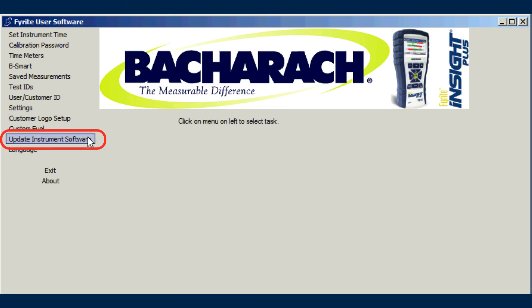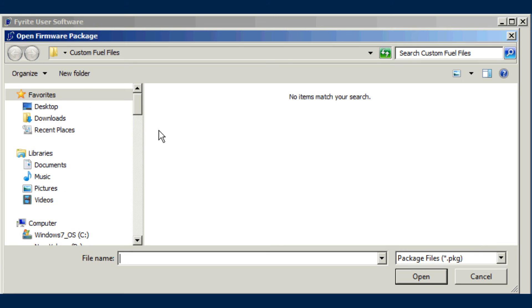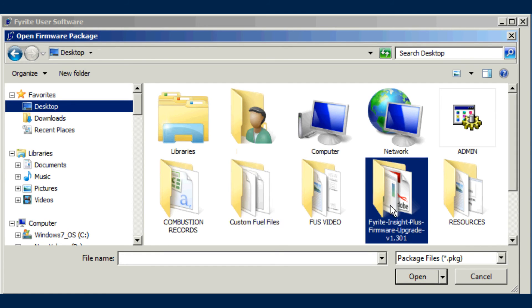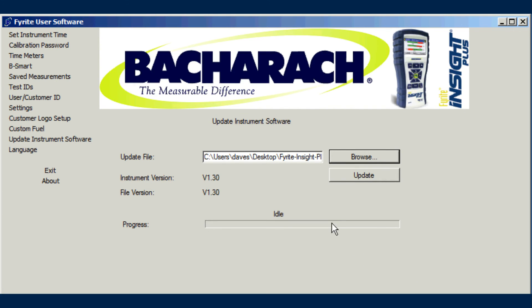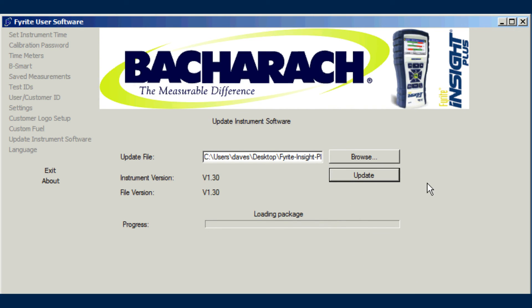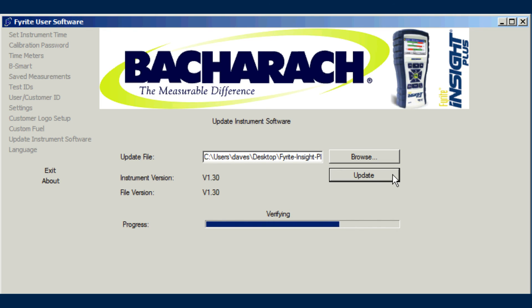Periodically, software updates are available for analyzers. Bacharach provides a PKG update file which you copy to your PC. Then use the Update Instrument Software menu item to transfer the new software from your PC to your analyzer. Use the Browse button to locate the saved software file on your PC, then press Update to download the new software file into the instrument. The software will display a progress chart showing the status of the programming.